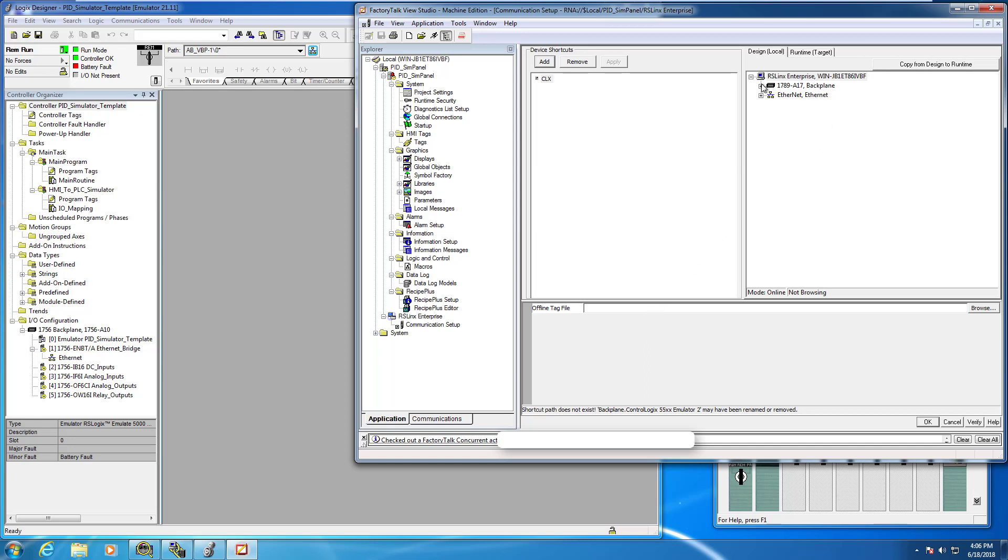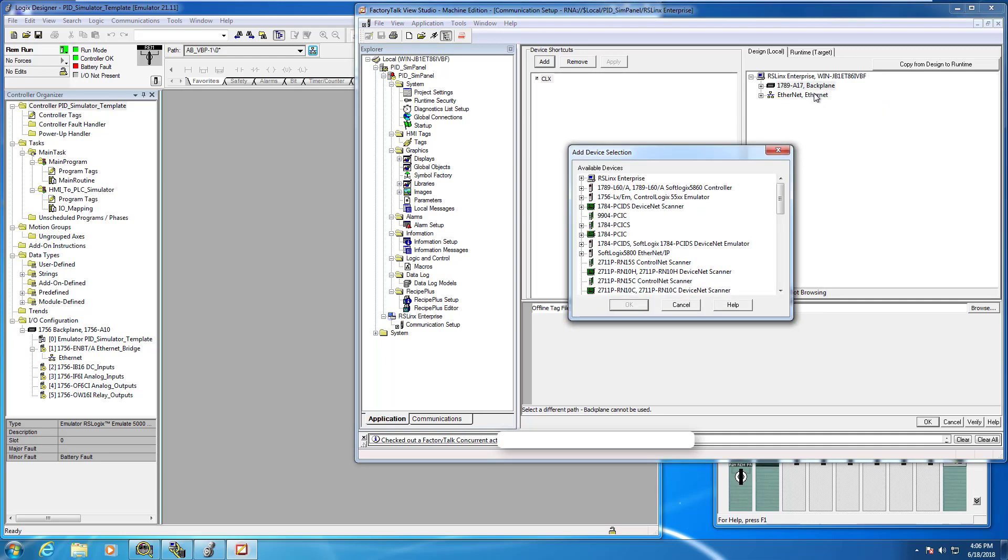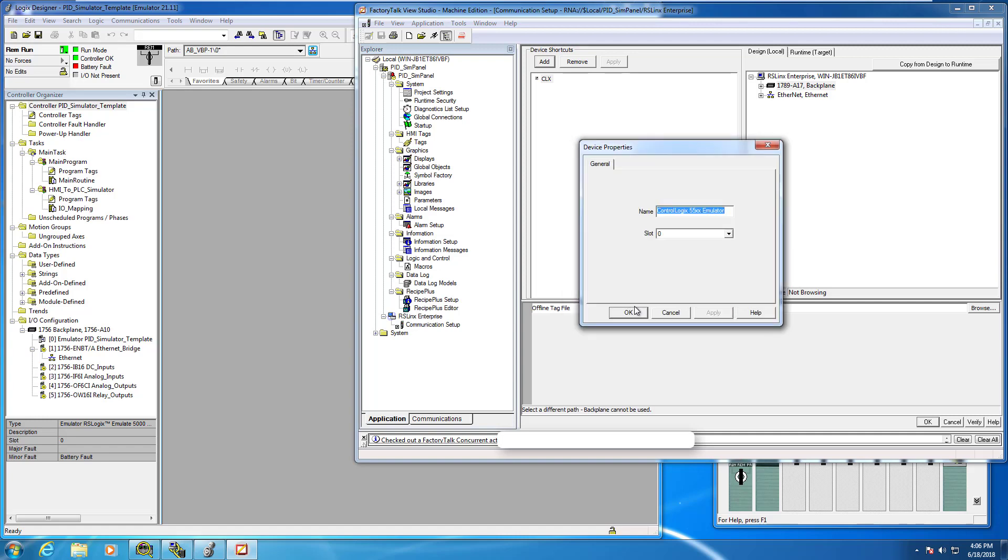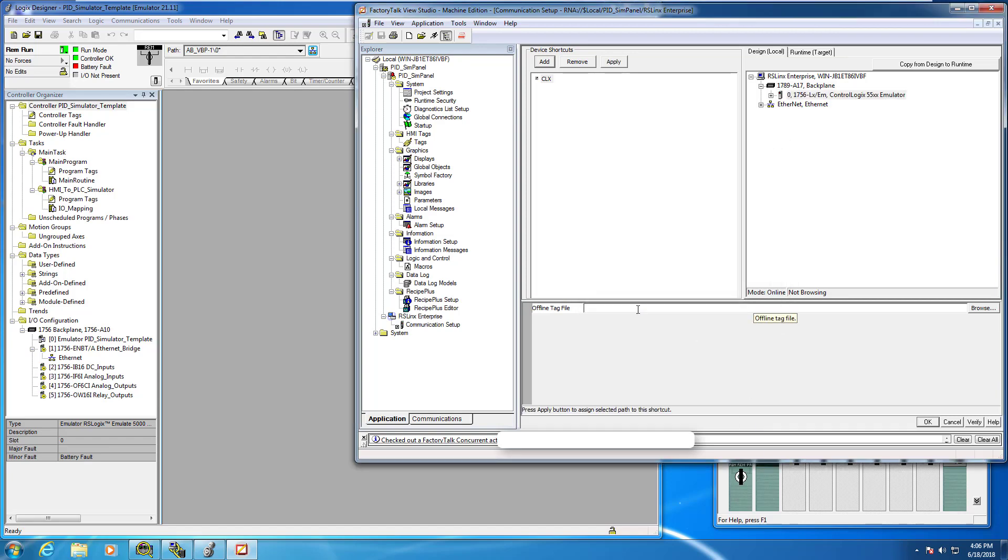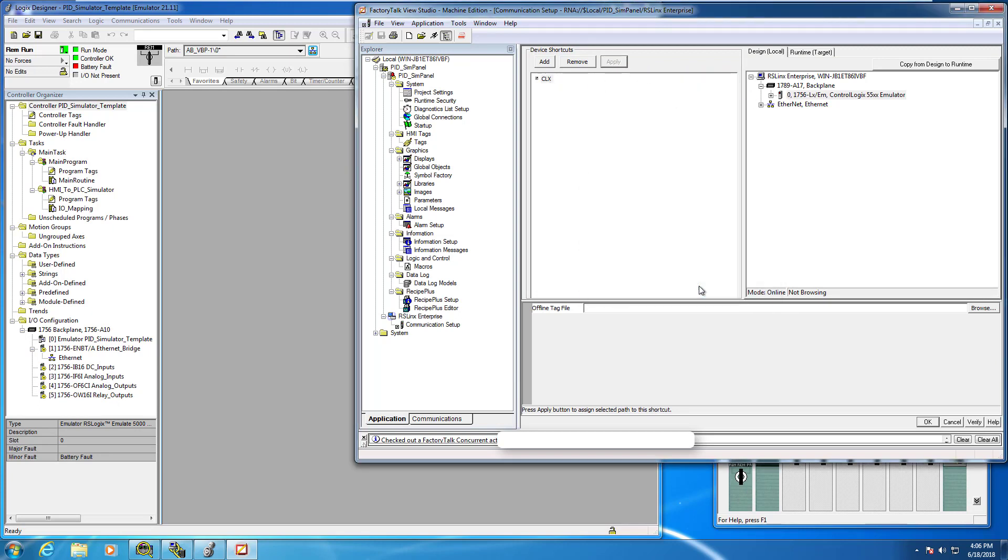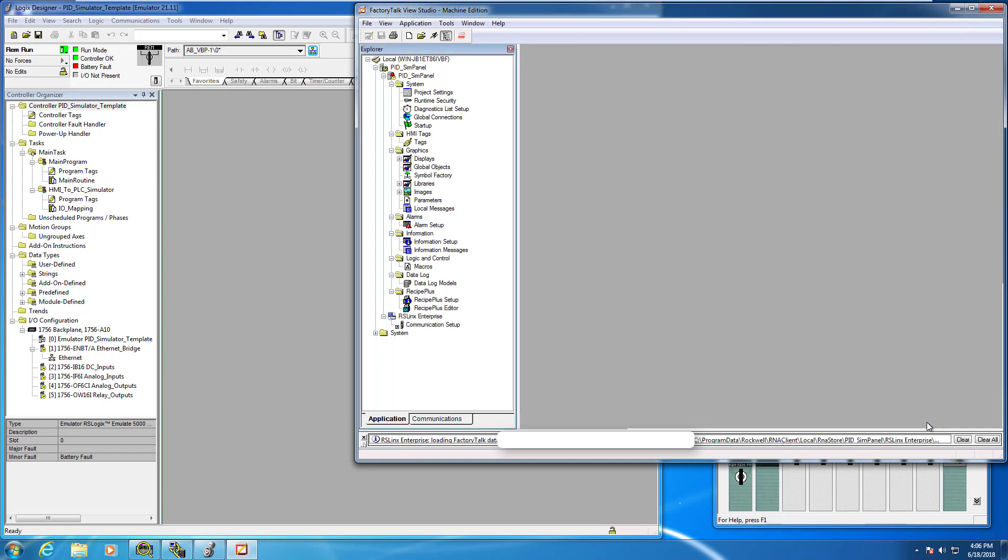No problem, it's very straightforward. I'm going to right click on the 1789 backplane here, add device, and you want to look for the emulator controller. I'm going to choose the major revision 11 here and click okay. Our emulator is in fact in slot zero down here, so we'll click okay. What you want to make sure of is just that you apply these changes. Click yes and that should be it.